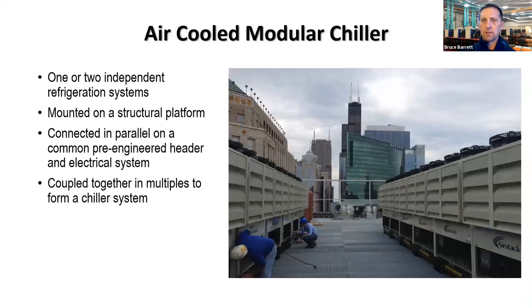So, modular chillers, quick review. It is two independent refrigerant circuits per module. It can be mounted on a structural platform. They're all connected in parallel, so they can be controlled in a variable primary flow situation, primary, secondary. They do share a common master controller.